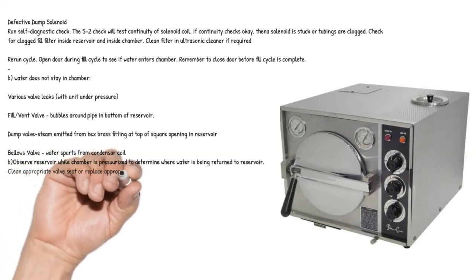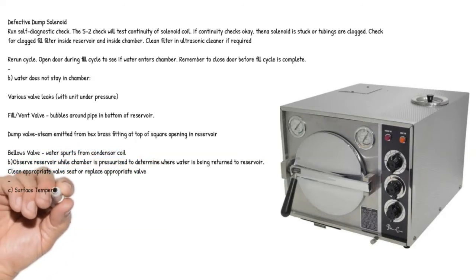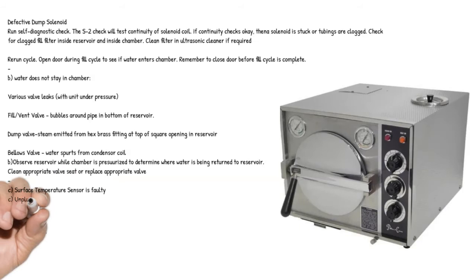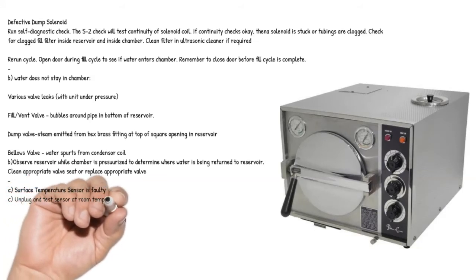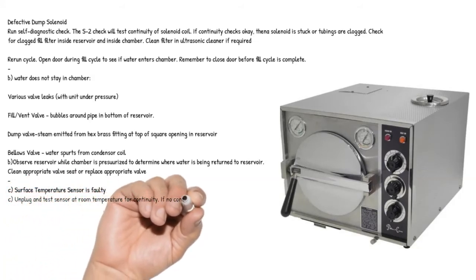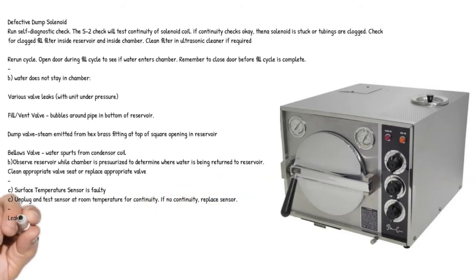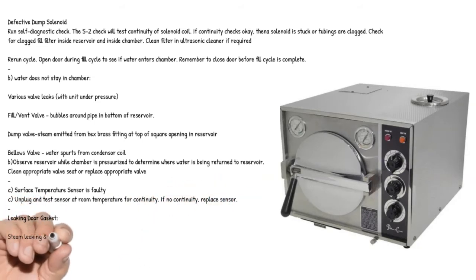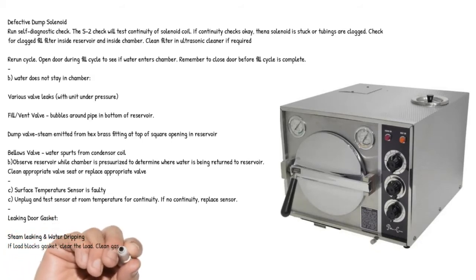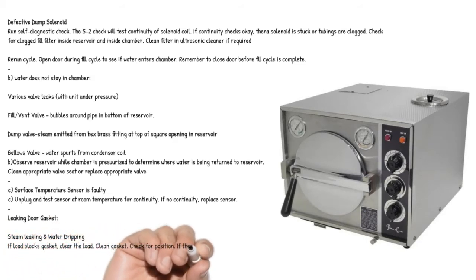C. Surface temperature sensor is faulty. C. Unplug and test sensor at room temperature for continuity. If no continuity, replace sensor. Leaking door gasket. Steam leaking and water dripping. If load blocks gasket, clear the load. Clean gasket. Check for position. If these fail, replace gasket.